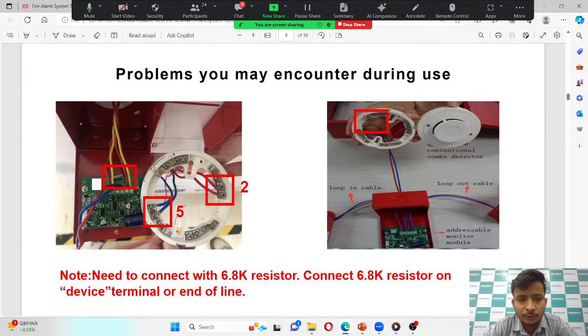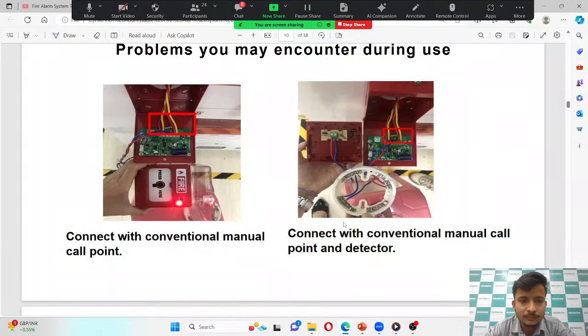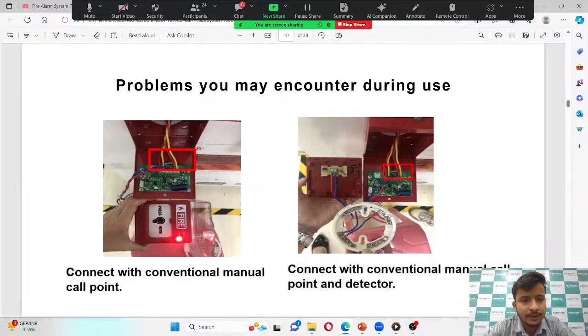Problems you may encounter during use. When you are adding a detector with the help of this monitor module, you need to connect a 6.8 kilo ohm resistor. As you can see here, you need to add one 6.8 kilo ohm resistor with the detector, or at the end of line of the end device, the last device of the loop. And the same if you are adding an MCP and detector with this monitor module, you need to add that resistor, as you can see here.